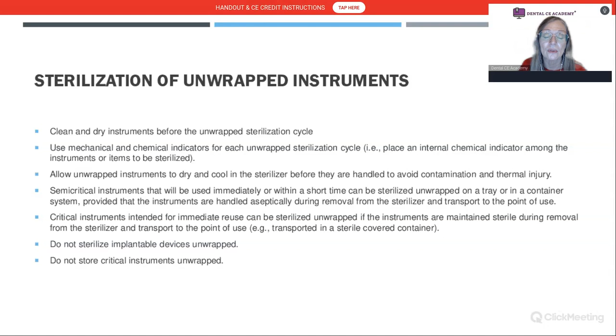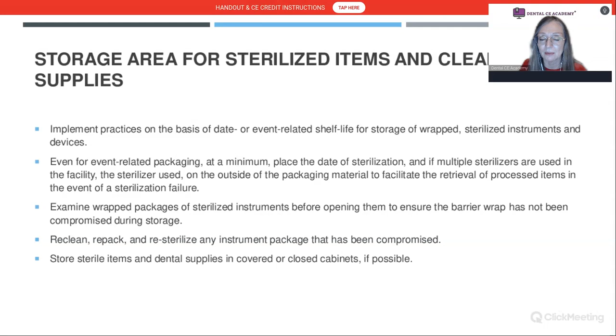Some states require you to label the packets, either date related or event related. So date related, you are going to stamp it or label it with the date that it was autoclaved and the autoclave that it came out of. And that state may require you to re-autoclave those every 30 days if you haven't used it. Event related means in that state, they're okay until there's a tear or rip or the tape falls off the package, and then we've got to reprocess. And we start over with ultrasonics, and then we autoclave.